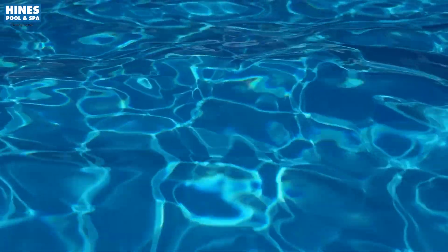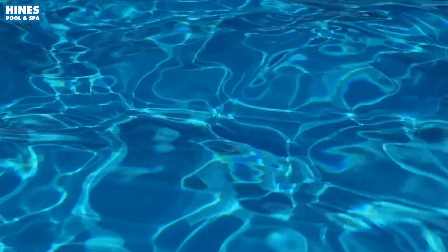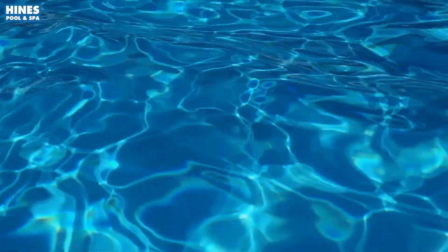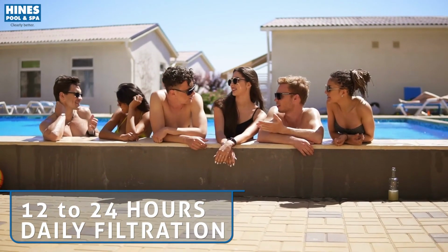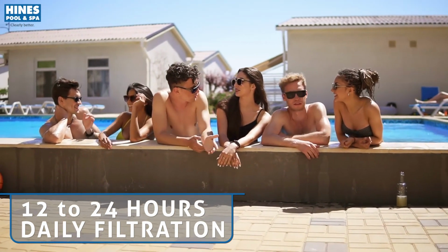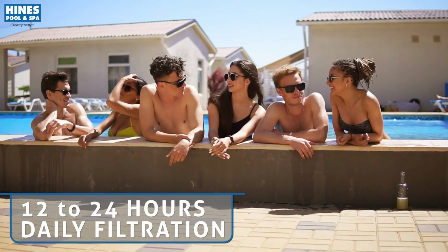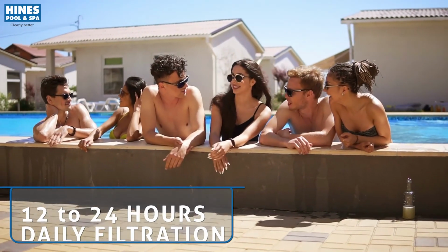That's called a turnover. Quite a few pools require 2 turnovers to keep the water clear, especially in hot weather, and maybe more turnovers, depending on the number of people using the pool and weather conditions. For best sanitation and filtration, most pools need at least 12 to 24 hours of filtration daily. Hotter weather requires longer circulation times.